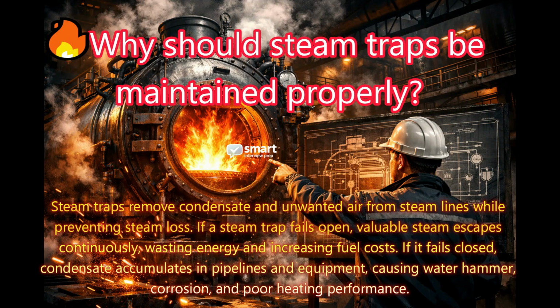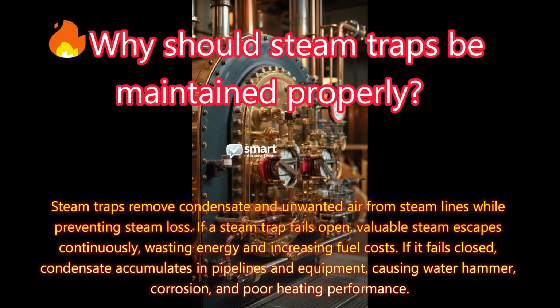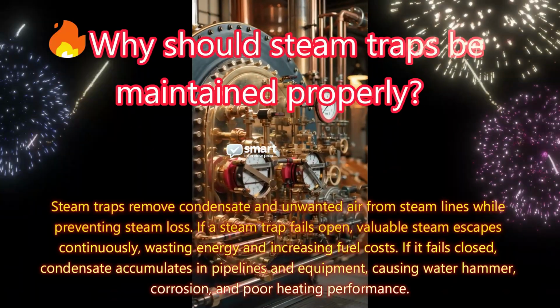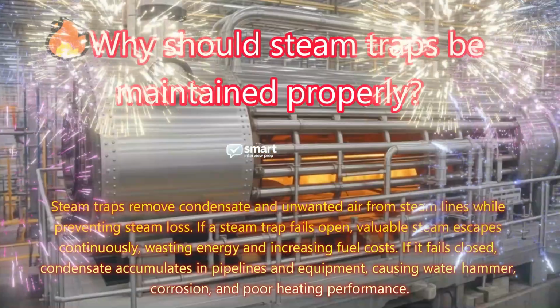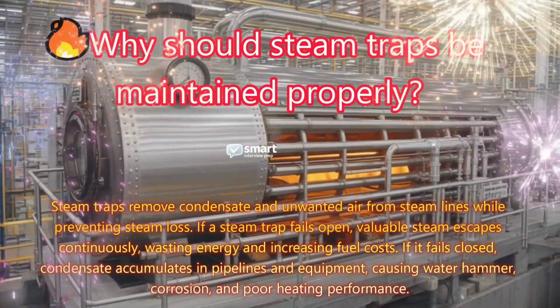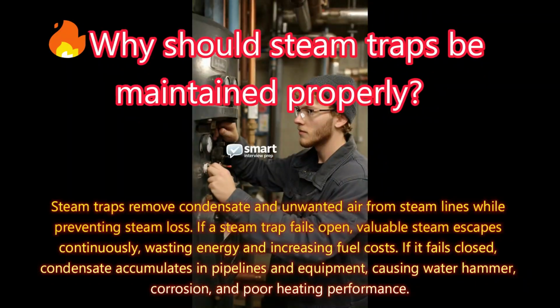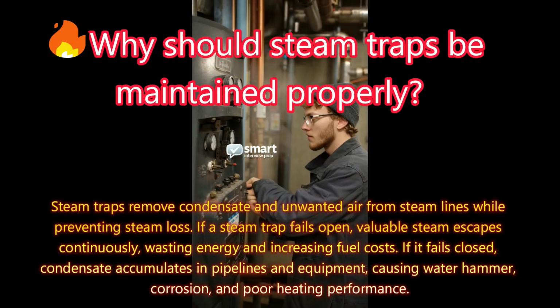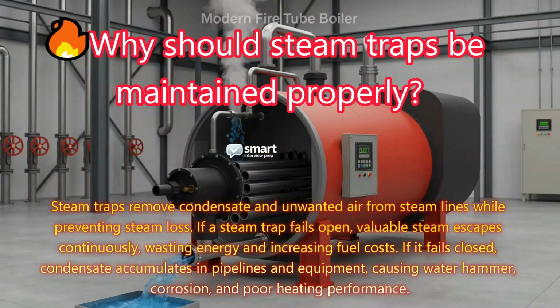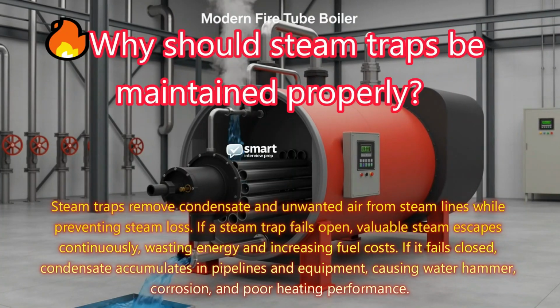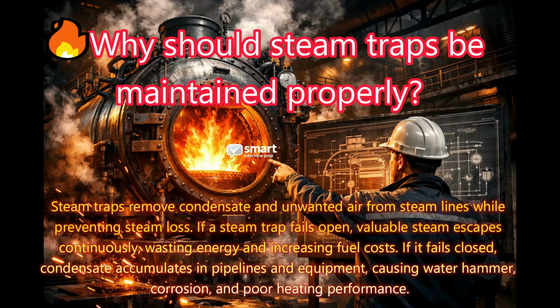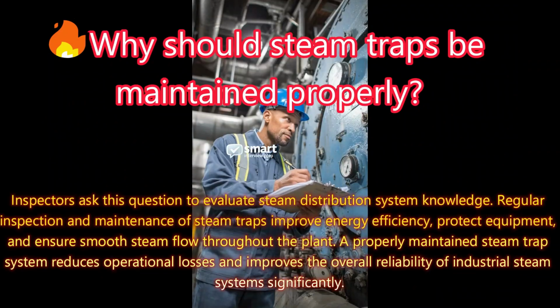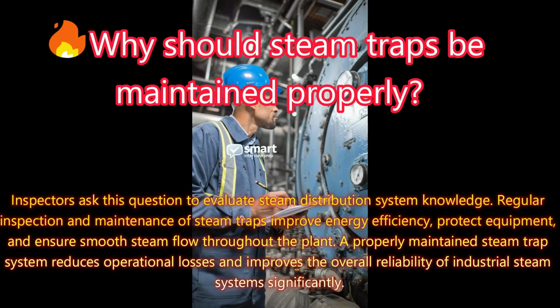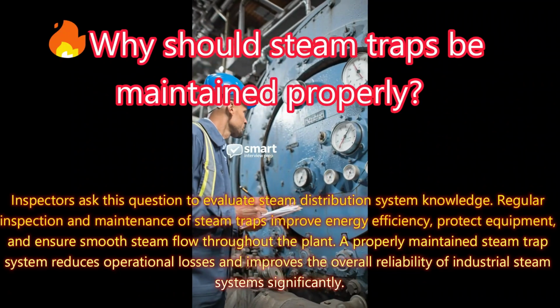Answer: steam traps remove condensate and unwanted air from steam lines while preventing steam loss. If a steam trap fails open, valuable steam escapes continuously, wasting energy and increasing fuel costs. If it fails closed, condensate accumulates in pipelines and equipment, causing water hammer, corrosion, and poor heating performance. Inspectors ask this question to evaluate steam distribution system knowledge.